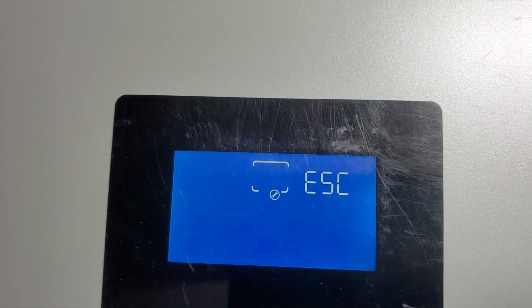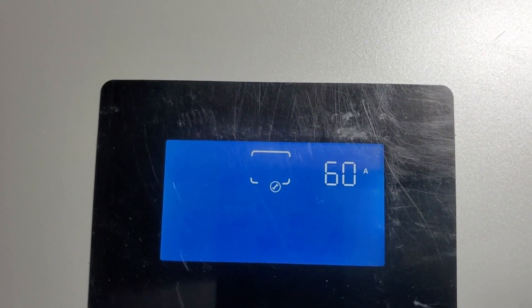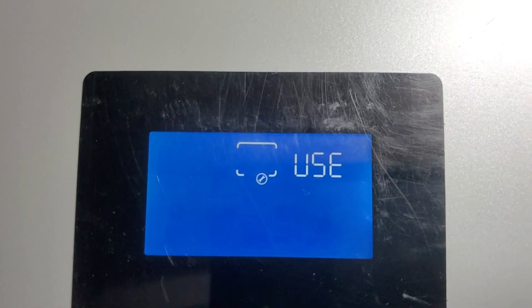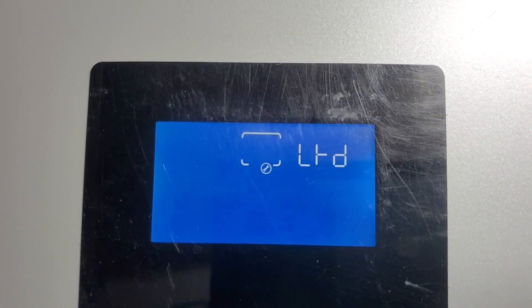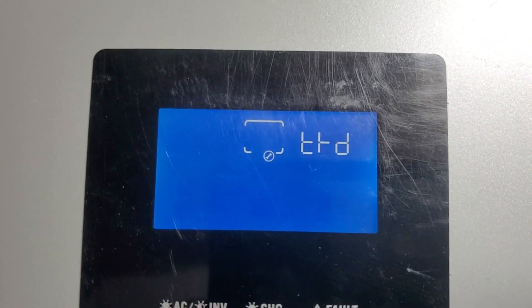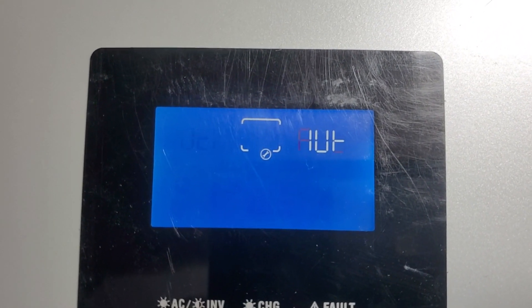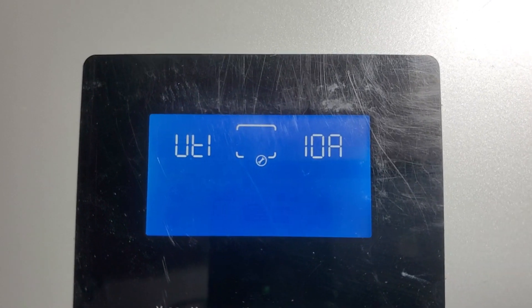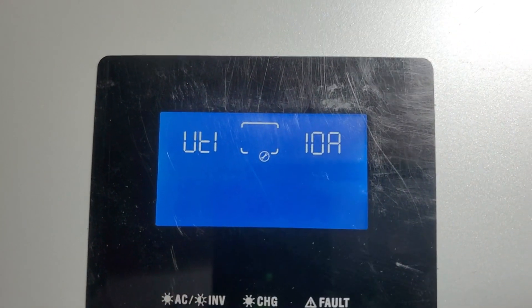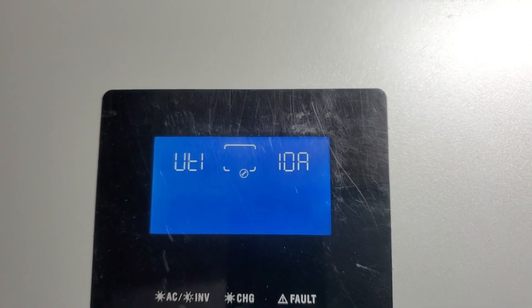So we can limit how many amps we charge from the generator. 60 amps is the total amps with solar and utility combined. Sorry for the noise but this 60 hertz. And that's the utility charging setting 11 is set to 10 amps. I've just adjusted it down for this video right now.